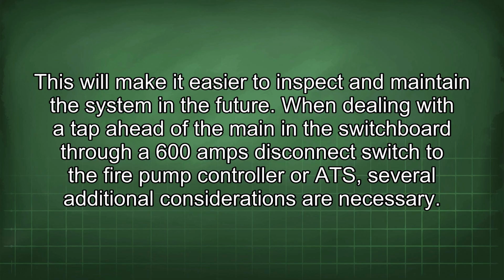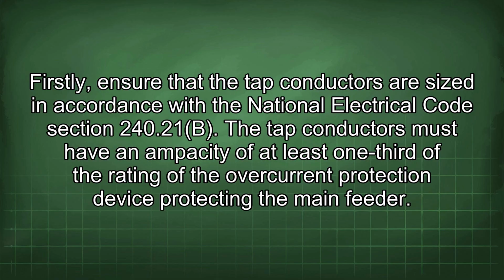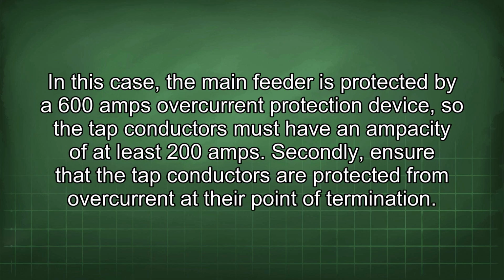When dealing with the tap ahead of the main in the switchboard through a 600 amps disconnect switch to the fire pump controller or ATS, several additional considerations are necessary. Firstly, ensure that the tap conductors are sized in accordance with the National Electrical Code Section 240.21(B). The tap conductors must have an ampacity of at least 1/3 of the rating of the overcurrent protection device protecting the main feeder. In this case, the main feeder is protected by a 600 amps overcurrent protection device, so the tap conductors must have an ampacity of at least 200 amps.